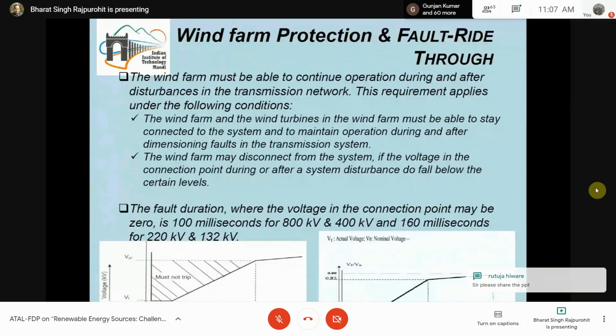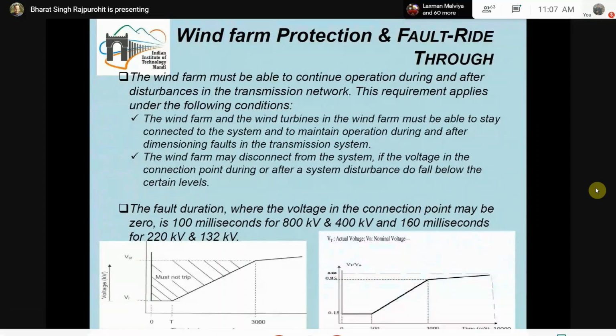In this diagram below, you can see the fault ride through capability curves for the Indian grid code, based on what voltage level the wind farm is connected to. Certain time limits are also there: 100 millisecond for 800 kV, and 400 kV, and 160 milliseconds for 220 kV and 132 kV. In this case, the Indian grid code expects that the voltage should not be below 15%. So this is not as strict as compared to the German grid code, right?